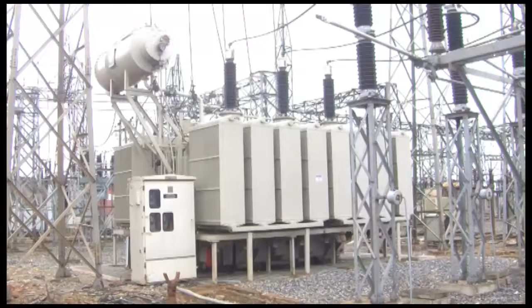The Assistant General Manager, Egbin Zone, of the Transmission Company of Nigeria said the project is of vital importance to the company and to Nigerians along the corridor it will cover. He explained: we have the capacity to be on 2 circuits from Shagamu to Ikorodu substation. It's going to increase our capacity and flexibility, in the sense that when one line goes off, the other will take over. The old line is reconductored to carry 90 MVA, but the single line of this new construction is going to carry 126 MVA, so we have a combined capacity of 2 by 126 MVA.